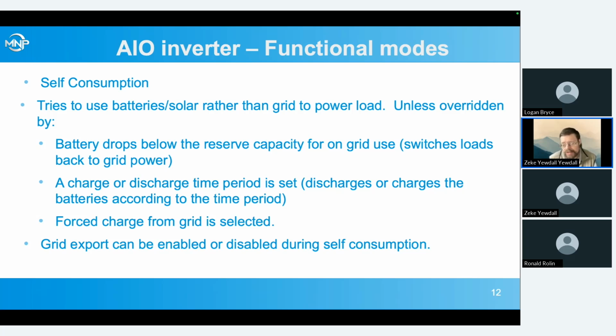You also have the choice of picking what is your grid export level. Say you've got an interconnection that can only handle 4 kilowatts of export, but you've got a 12 kilowatt array. You could do self-consumption and then tell it, you've got extra solar, you can export up to 4 kilowatts, but not any more than that, and it will limit to that.